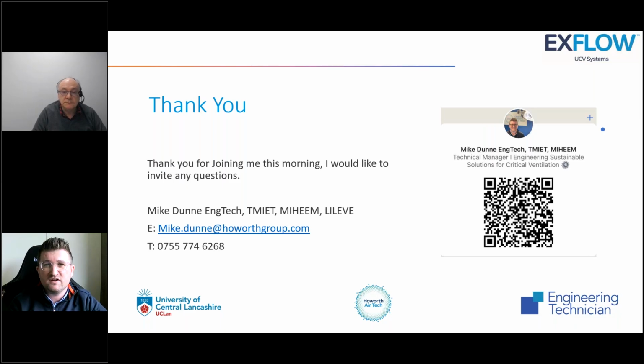We're never going to use an operating theatre when the HVAC goes to setback, because the dilution in the space isn't good enough. But we also have other considerations to make. The hospital that I showed you on the screen didn't consider the background temperature of the operating theatre, so it would switch the vent off. That mattered less on that site because it sat in the central core of the building. But at the 60-year-old hospital that I looked at, their theatres went to an adjacent outside wall, so the delta T across that wall was greater than it would be inside the core of a building.